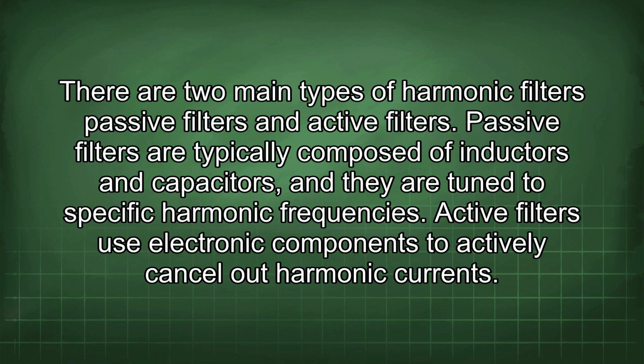There are two main types of harmonic filters: passive filters and active filters. Passive filters are typically composed of inductors and capacitors, and they are tuned to specific harmonic frequencies. Active filters use electronic components to actively cancel out harmonic currents.